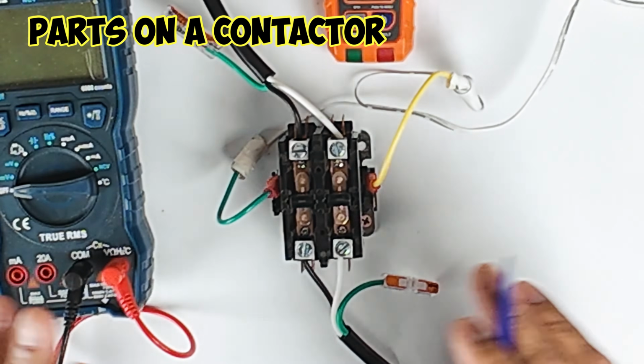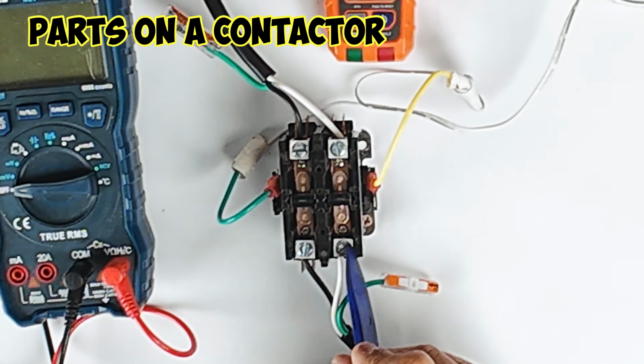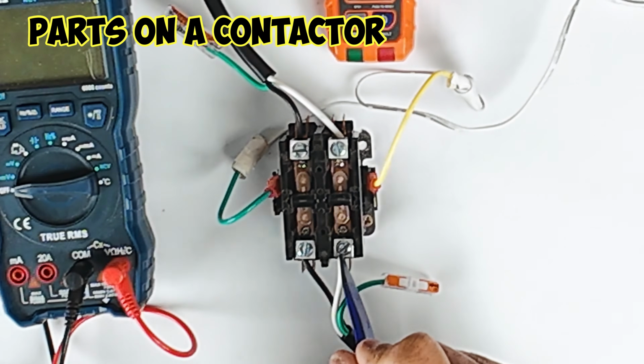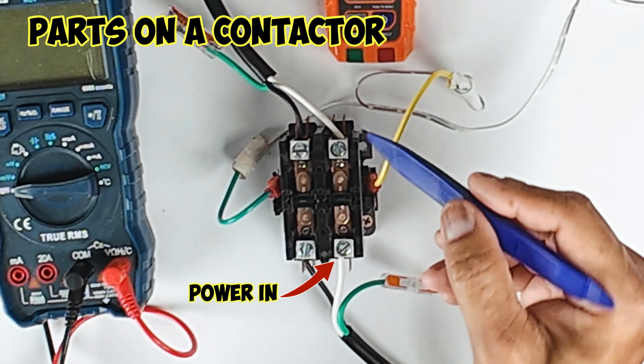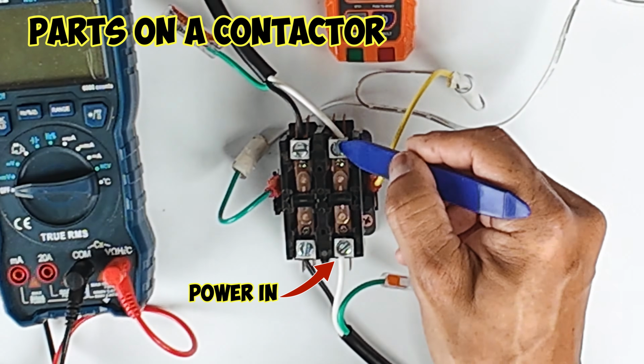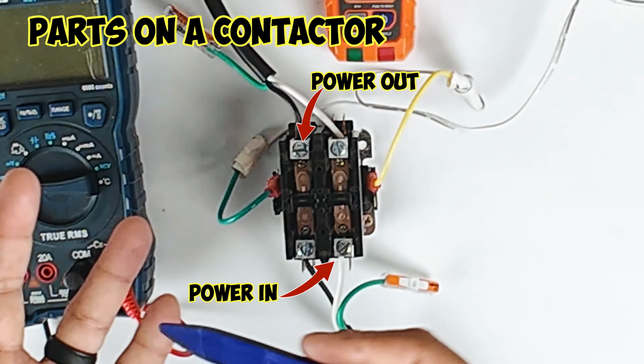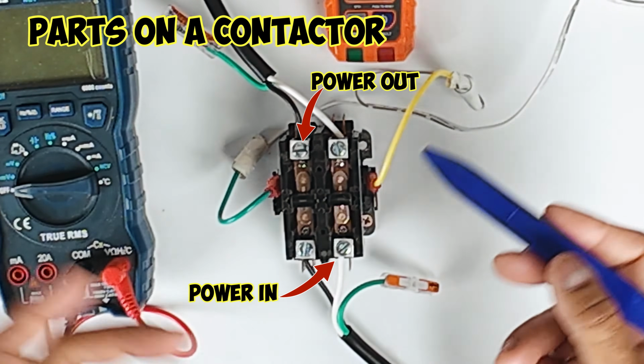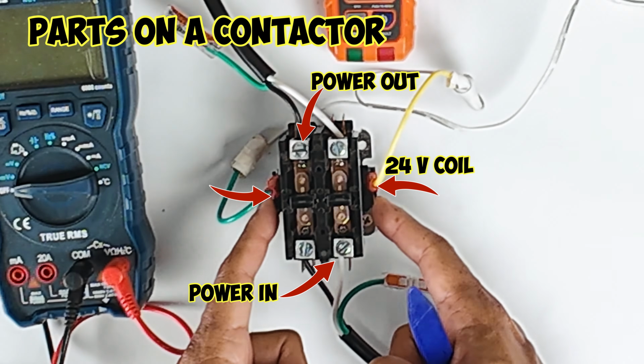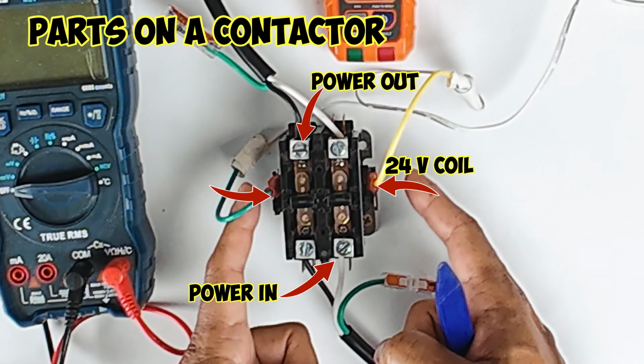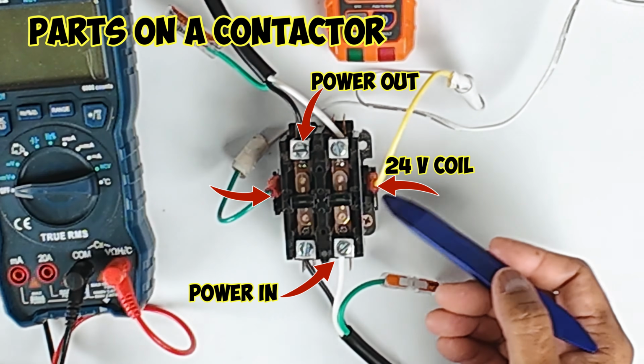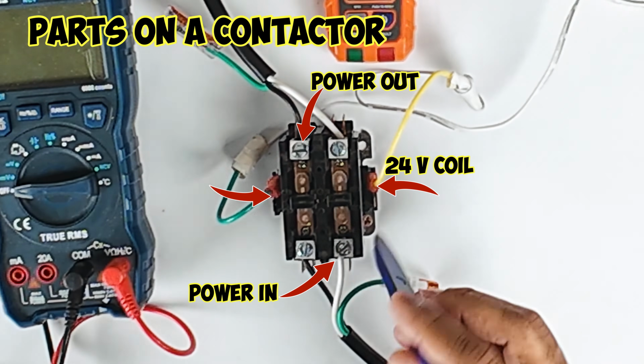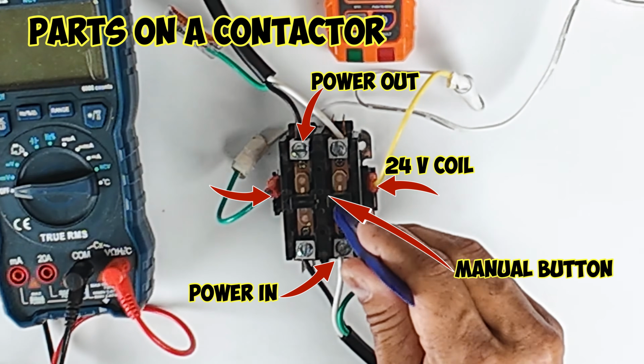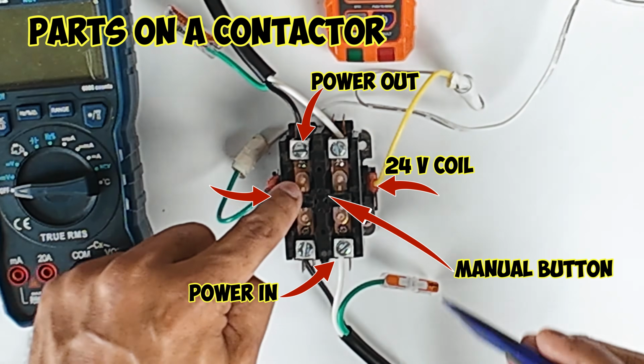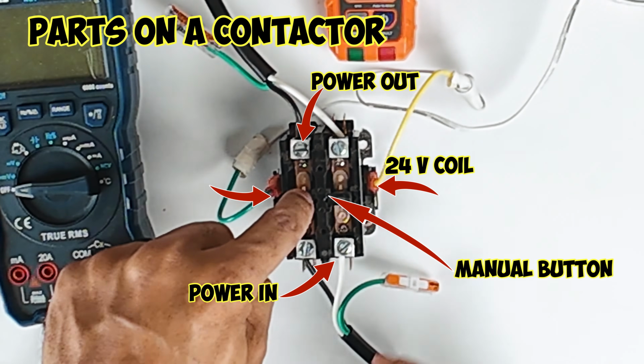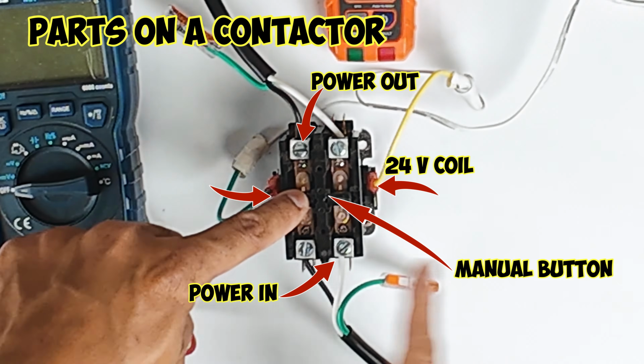All contactors are made up of the same parts. You have the bottom side of your contactor, which is where your incoming voltage comes in. You have the opposite side is where your voltage goes out to your compressor or your fan motor or your capacitor. And you have the low voltage side of your contactor, which is powered by 24 volts, which is coming from the inside of your house, from your thermostat. And last but not least, you have a button on the front, which is a manual button, as you can see here. This is controlled by the electromagnetic voltage that's passing through here.